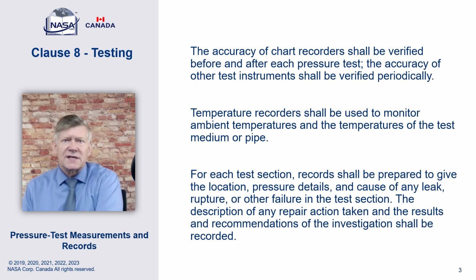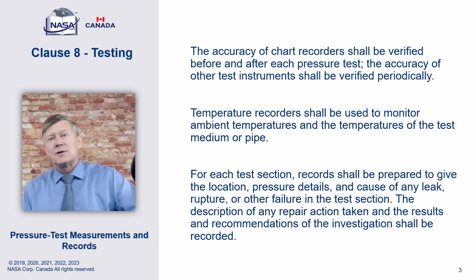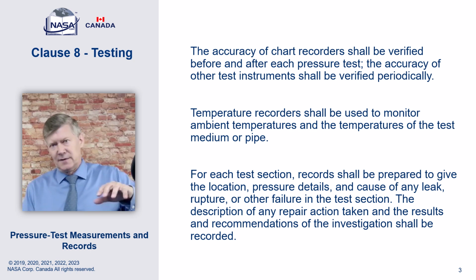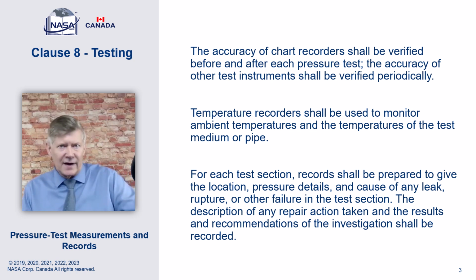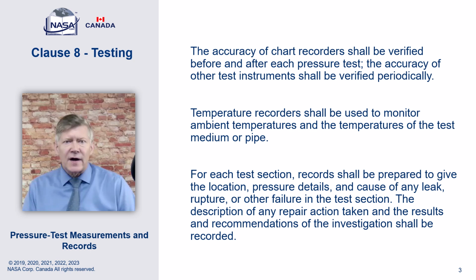So 8774 says that temperature recorders shall be used to monitor the ambient temperature and temperatures of the test medium of the pipe. That is a really valuable tool if you do have an anomaly and you need to verify it, right? That gives you something, because a lot of times, in most cases, pressure fluctuations will be directly correlated to temperature variations. 8775 says that for each test section, records shall be prepared to give the location, pressure details, and the cause of any leak, rupture, or other failure in the test section, the description of any repair action taken, and the results and recommendations of the investigation shall be recorded.